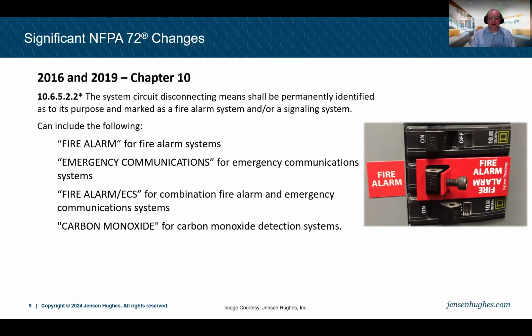Most fire alarm systems are protected by a circuit breaker on the primary power. So having these kinds of words listed, making it very clear where the circuit breaker for our fire alarm systems are, identifying it as to what kind of system. In 2019, the labeling moved to Annex A material as suggestions, but you get the idea to make sure we understand where our circuit breakers are for our fire alarm panel. And this is also a National Electric Code requirement, so NFPA 70 also applies to our information here.